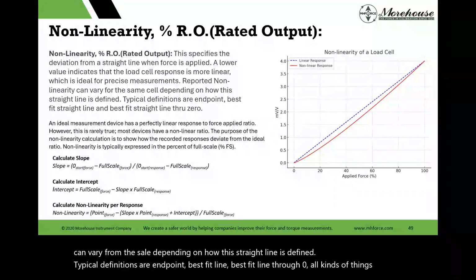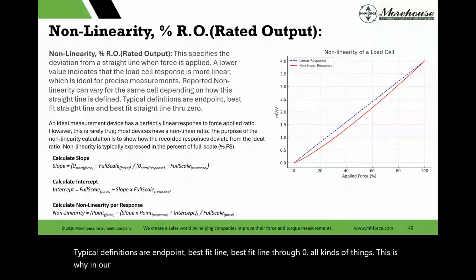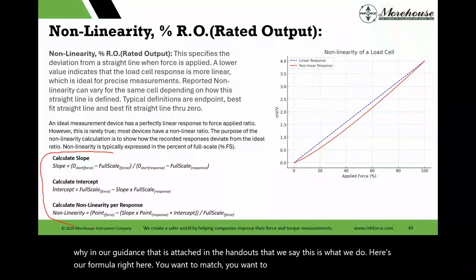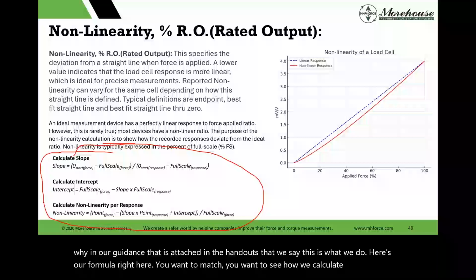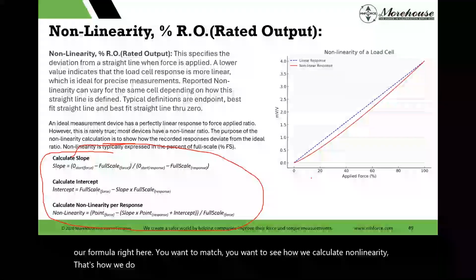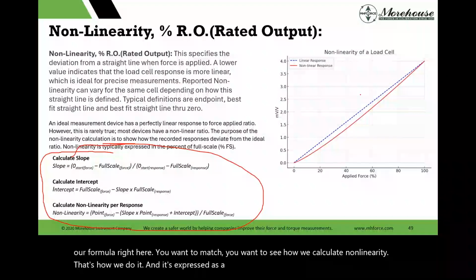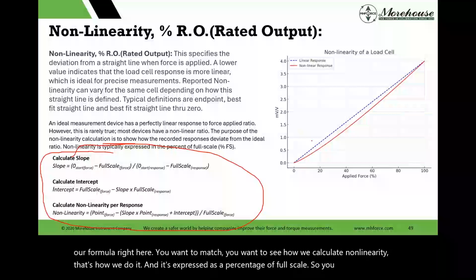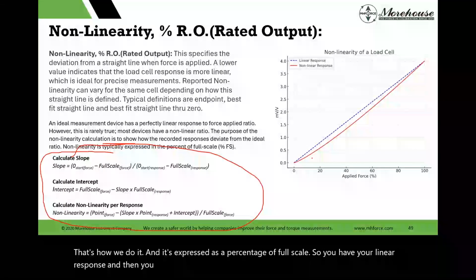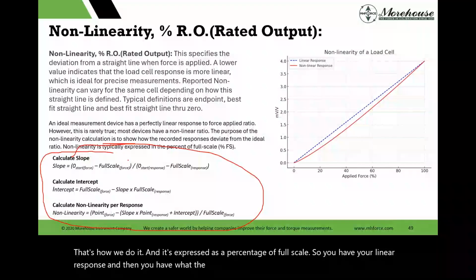This is why, in our guidance that is attached in the handouts, we say this is what we do. Here's our formula right here. You want to match? You want to see how we calculate nonlinearity? That's how we do it, and it's expressed as a percentage of full scale. So you have your linear response, and then you have what the load cell is actually doing, in red.